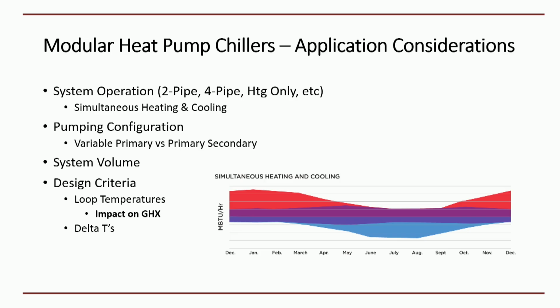These are compressorized pieces of equipment. And then loop temperatures. There is a wide range, and Tim highlighted that on what this type of equipment can work within. You can do all different kinds of stuff, but the thing to pay attention to, just like what Tim mentioned with the high temperature equipment, is that there are trade-offs. Can you do a 140 degree leaving water temp on the hot water side out of a scroll compressor? Absolutely. Do you sacrifice a little bit on the COP as compared to maybe doing a 130 degree or 120 degree loop? Absolutely.